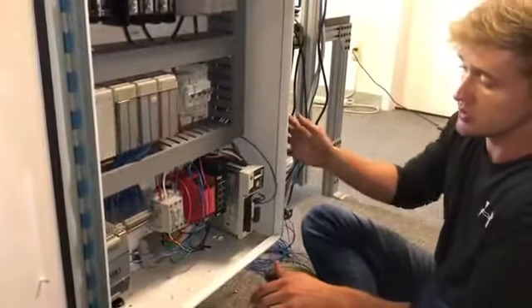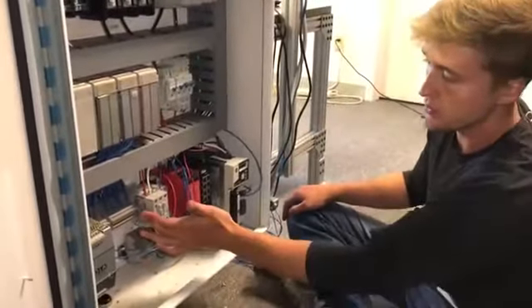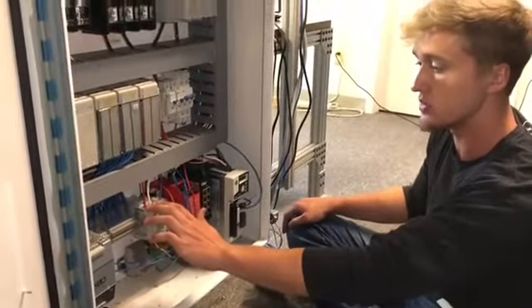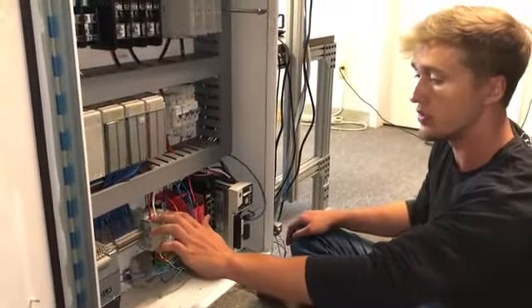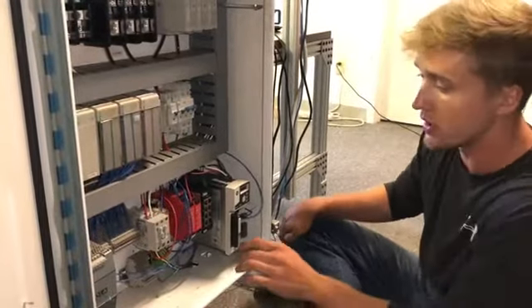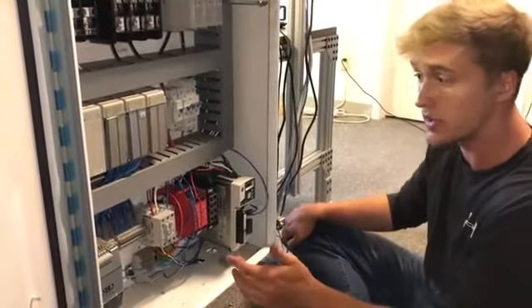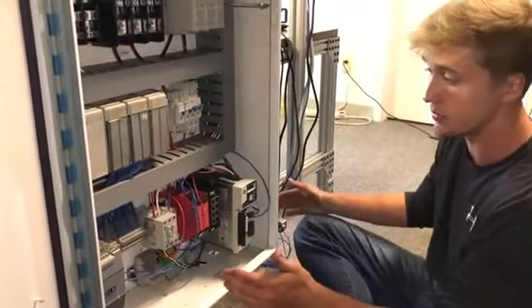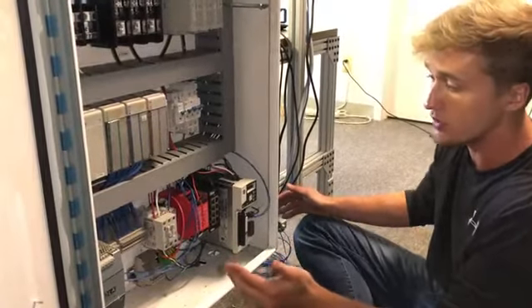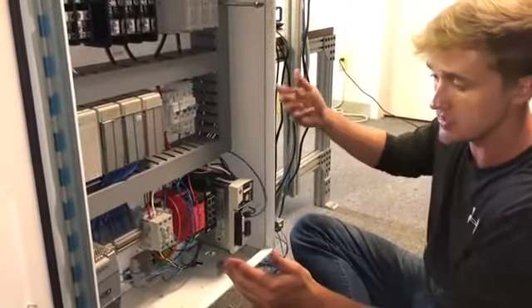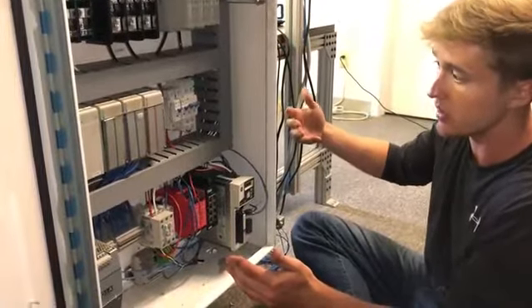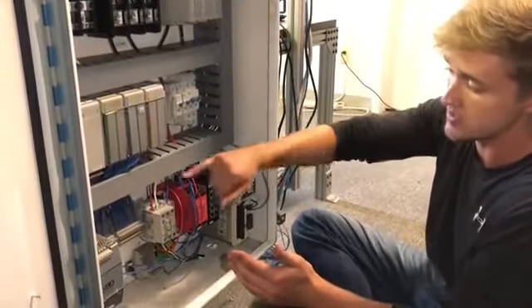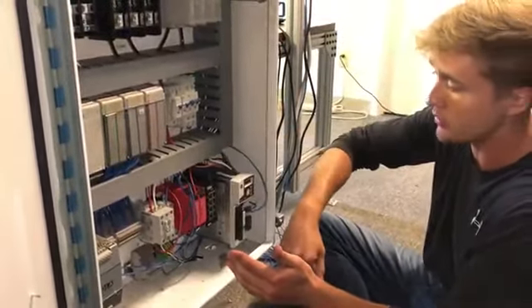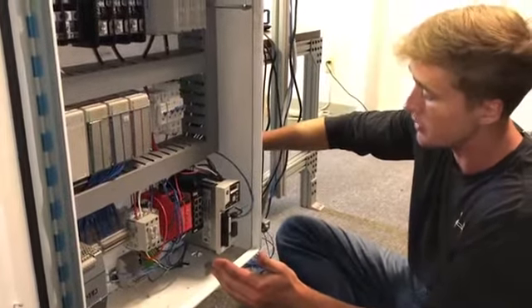On remark to the controls cabinet, a little added note, here's our motor starter. We're still uncertain whether or not we can control the coils of this motor contactor from a PLC output. So if for some reason we wouldn't be able to, we do have an isolation relay to be controlled from a 24 volt output to then send our 120 volt hot line through the motor contactor to the vacuum pump.